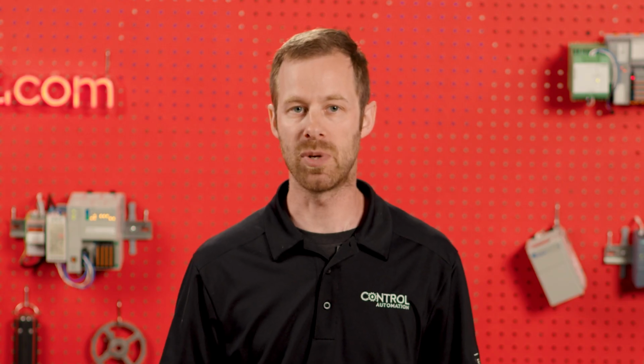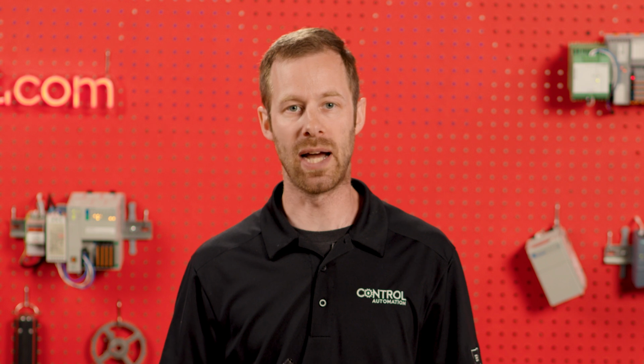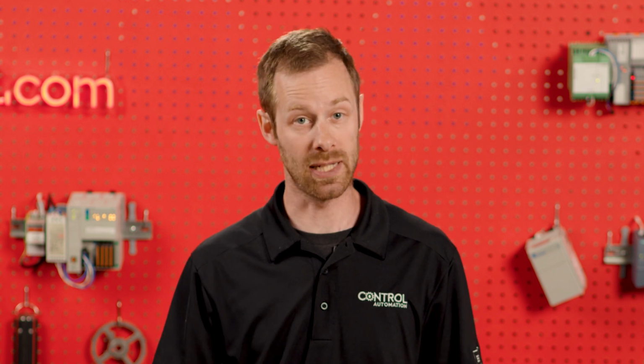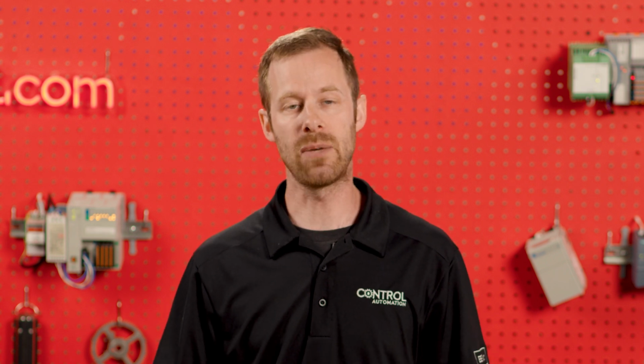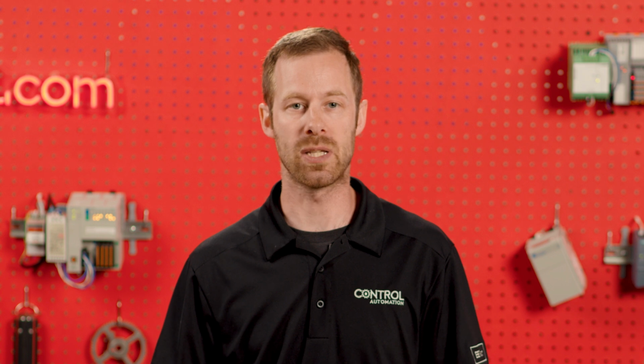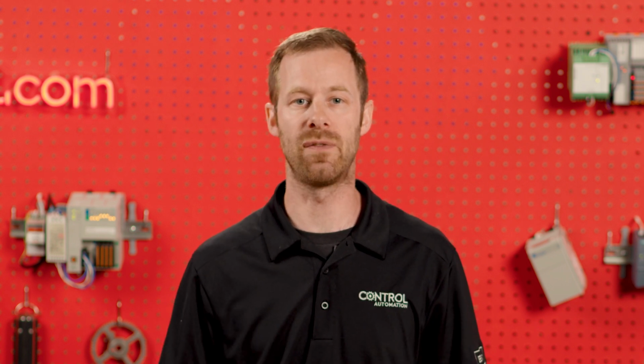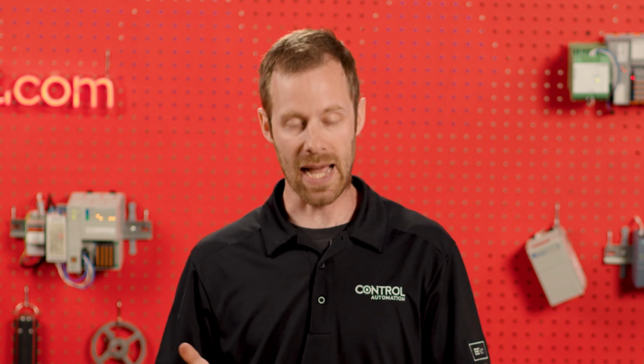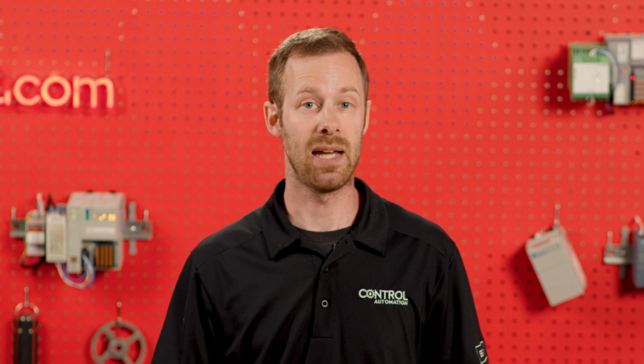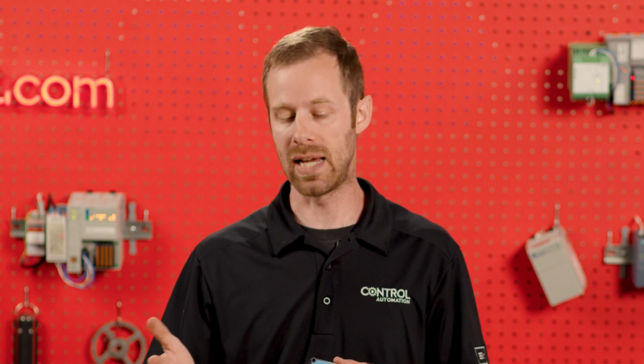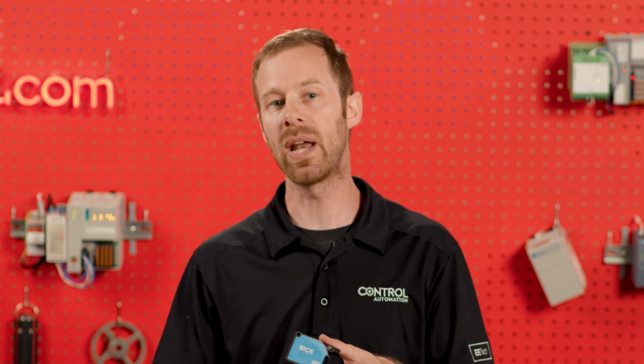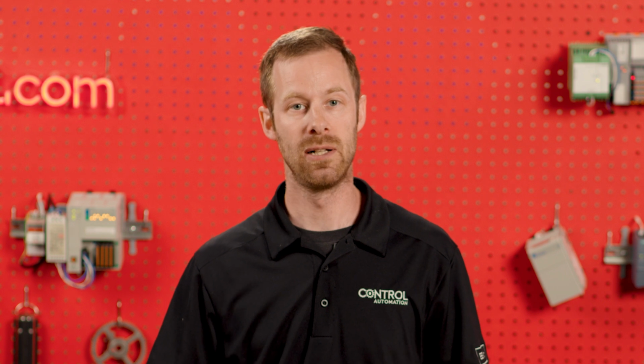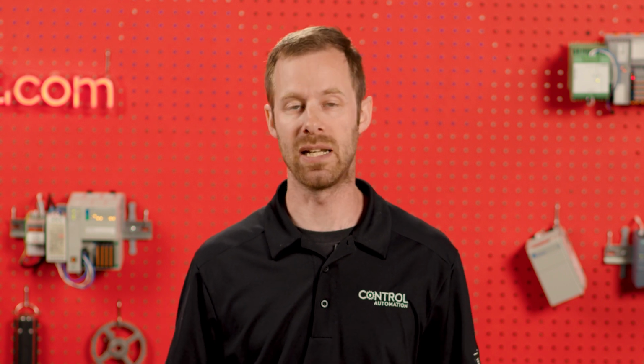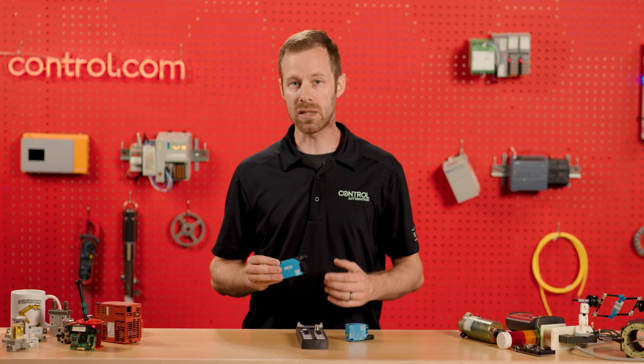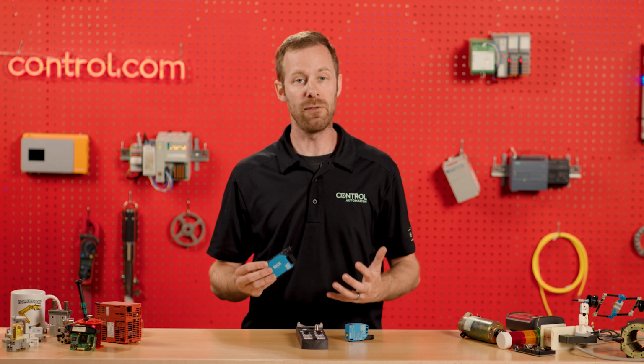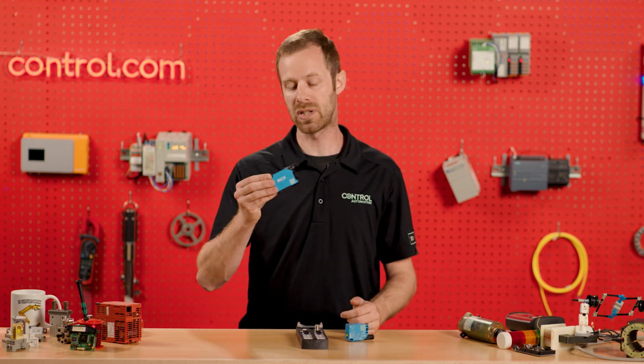We supply power, we supply ground, but that one signal wire, instead of just providing a trip point like a normal proximity sensor, we can supply multiple trip points, which can create a window or a range of operation. We can also get extra analog data. Analog means not only whether an object is within a field of view, but how far away it is as well. This is the difference between a proximity and a distance sensor. So by using this protocol, we've created a lot more flexibility in our system, even though we're still sticking with standard sensors.